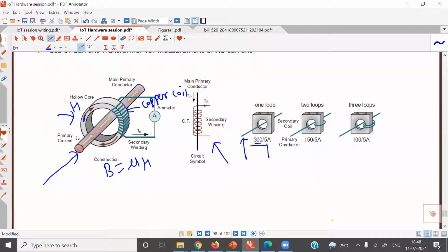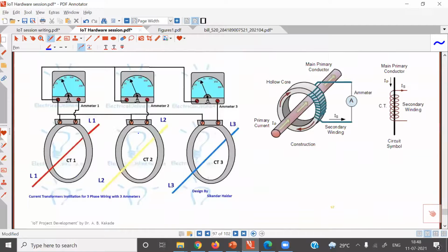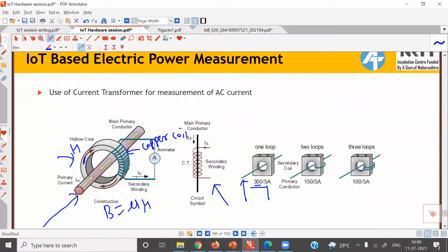The copper coil used in the CT has insulation. It is insulated with electrically non-conductive material like varnish. So if induced voltage goes in the range of kilovolt, like 5 kilovolts, 6 kilovolts, something like this, then this insulation in the winding gets damaged, and then nearby turns may get short circuited. So therefore, never operate CT without any resistor connected across the CT winding.